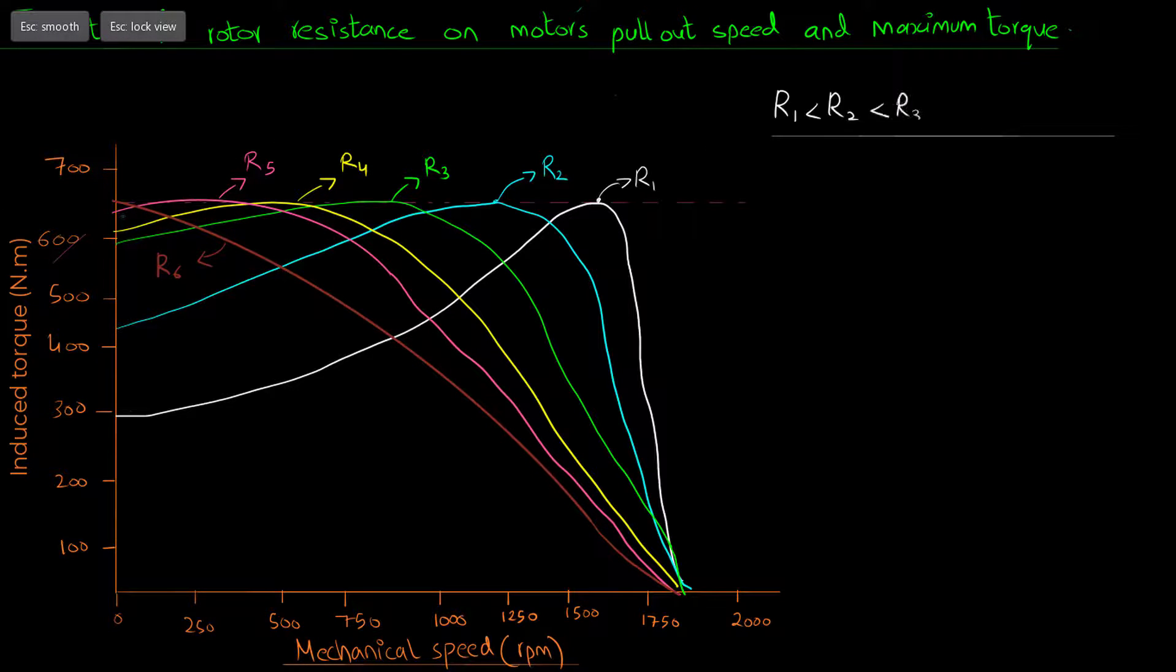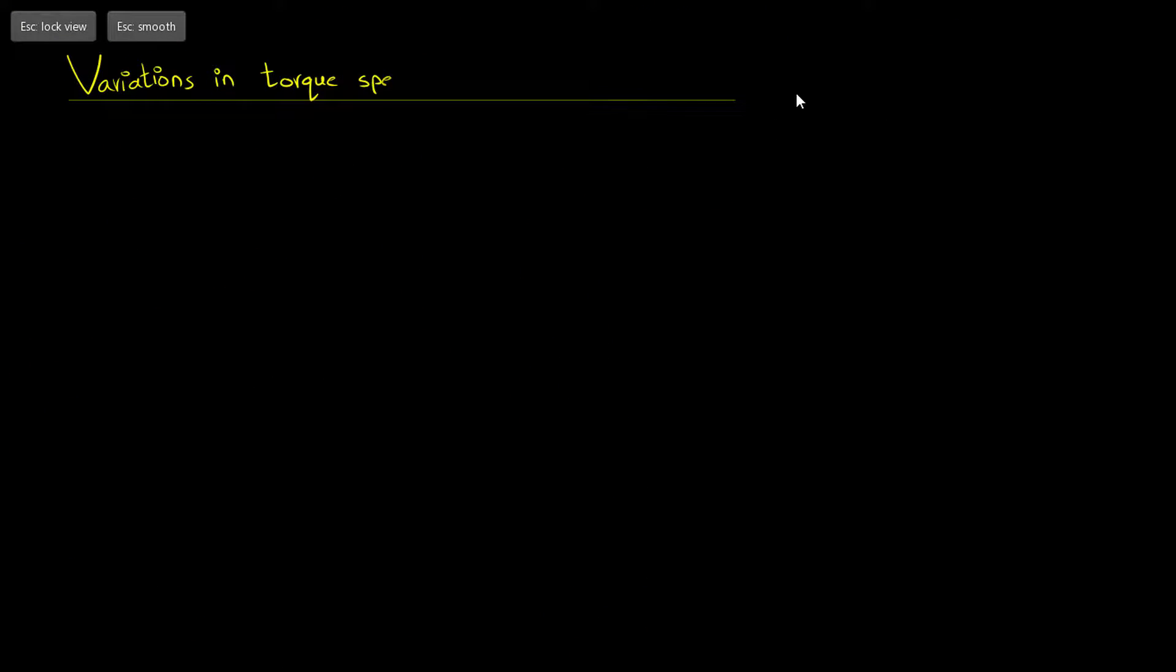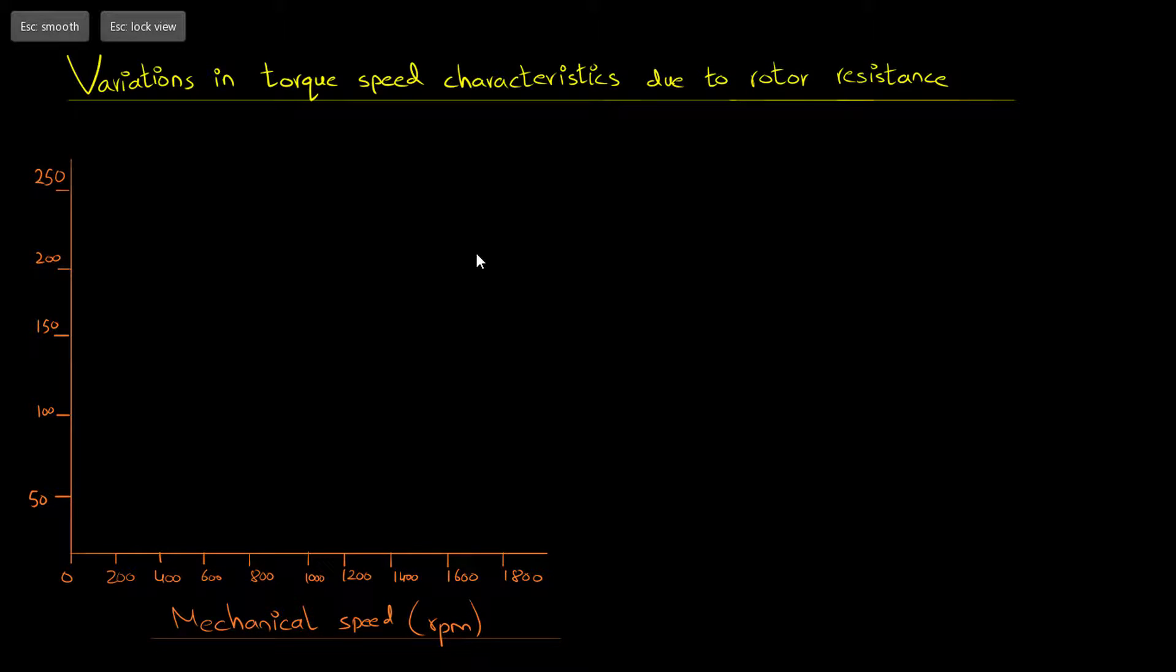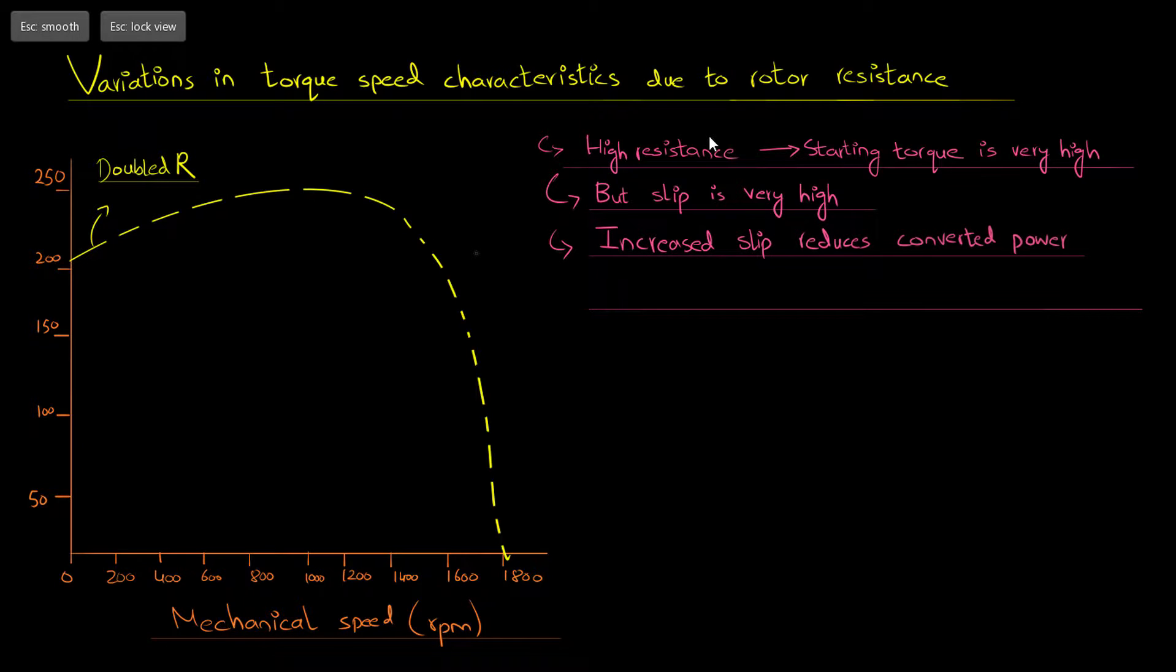Let's have a brief look at the variation in the torque speed characteristics of an induction motor due to its rotor resistance. If the rotor of the induction motor is designed with a high resistance, then the motor's starting torque is very high, but at the same time the slip is very high in normal operating conditions. This increased slip reduces the converted power, so the motor's efficiency is also reduced.